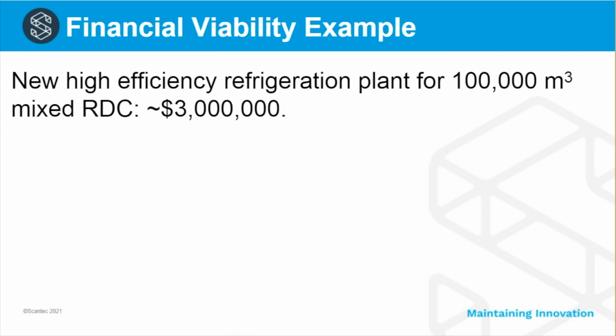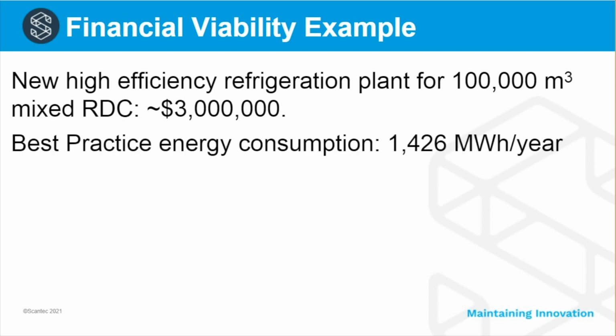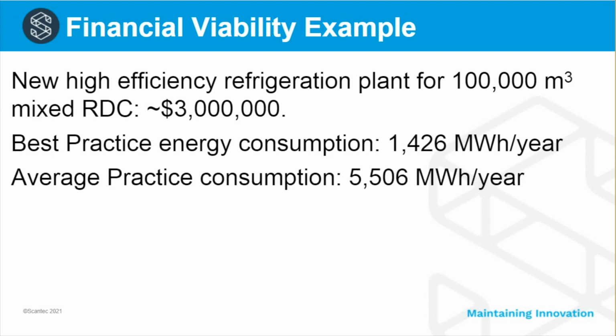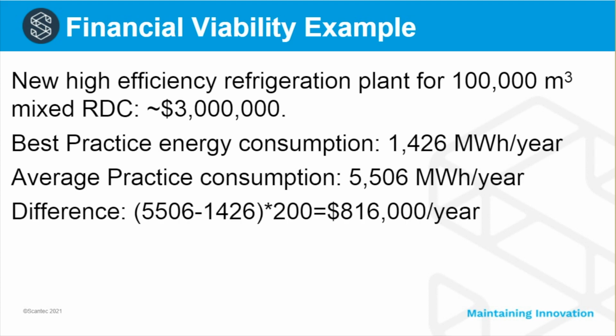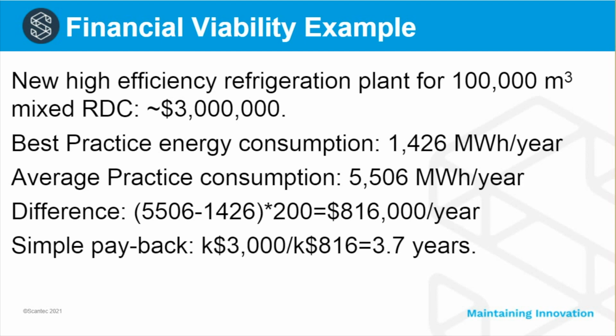Here's a financial viability example. What this is meant to illustrate is how big the difference is in money between an average practice warehouse and a best practice warehouse. So typically the refrigeration system for a warehouse like that costs $3 million in Australia. Best practice energy consumption is about 1,500 megawatt hours a year. Average practice energy consumption is about 5,500 megawatt hours per year. And that difference in money is about $800,000 a year. Now this is based on an electricity price of about 20 cents per kilowatt hour, $200 per megawatt hour. And if you divide 800,000 into 3 million, you get about 3-4 years.